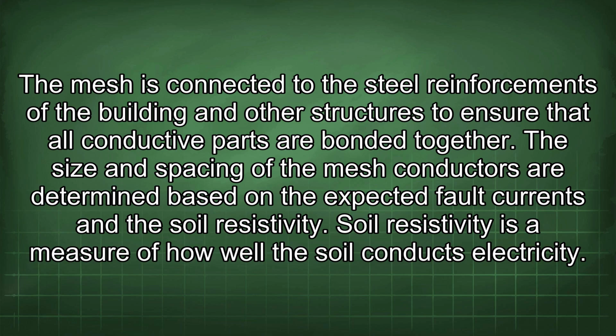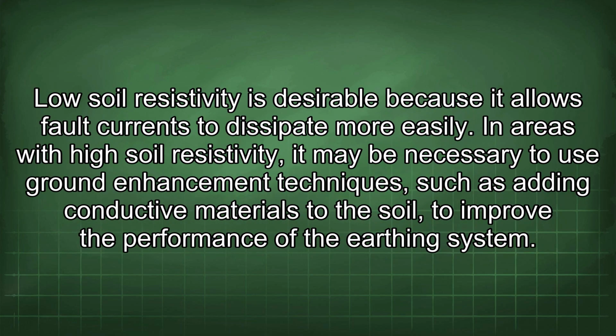The size and spacing of the mesh conductors are determined based on the expected fault currents and the soil resistivity. Soil resistivity is a measure of how well the soil conducts electricity. Low soil resistivity is desirable because it allows fault currents to dissipate more easily. In areas with high soil resistivity, it may be necessary to use ground enhancement techniques such as adding conductive materials to the soil to improve the performance of the earthing system.